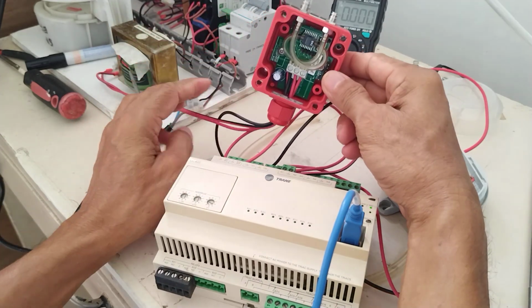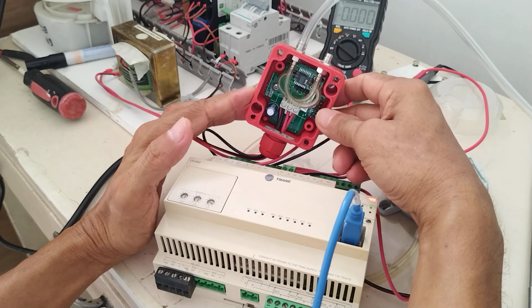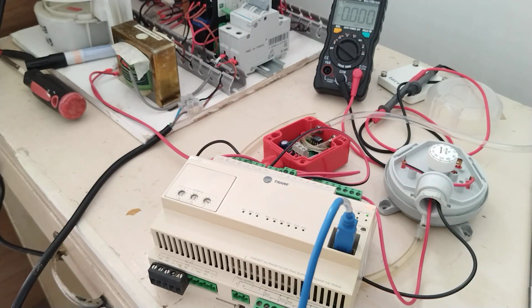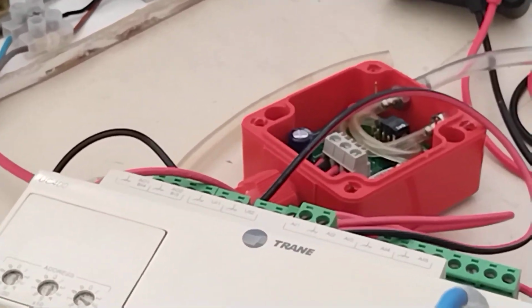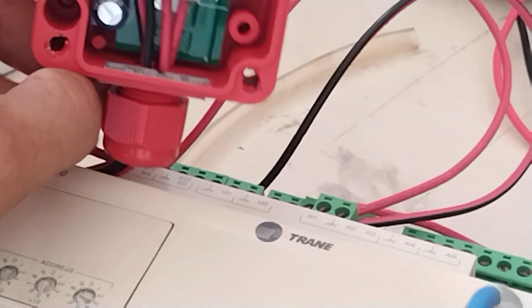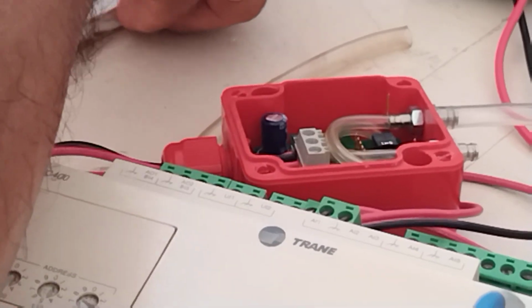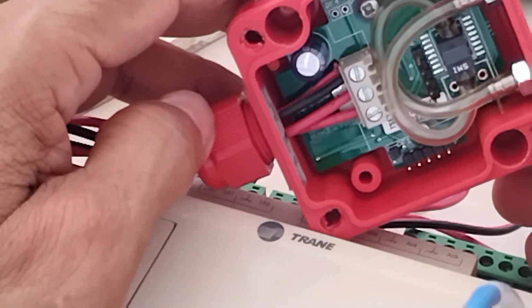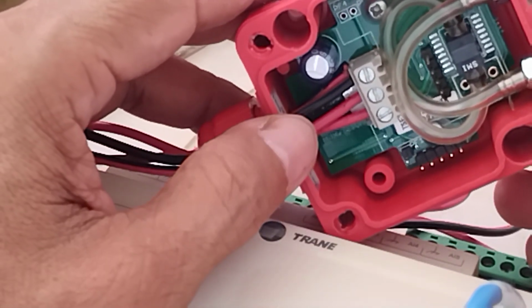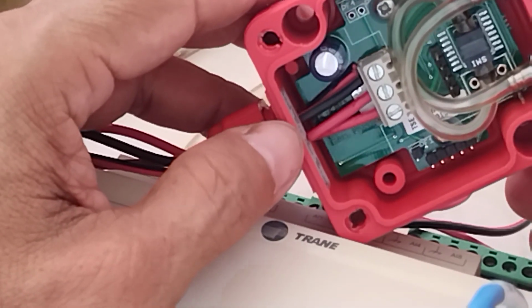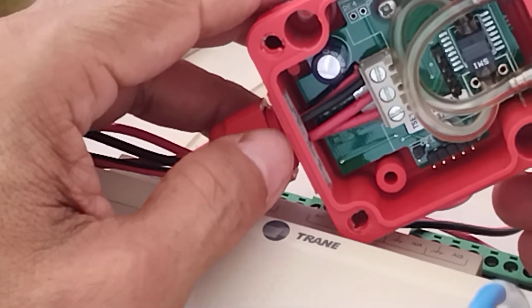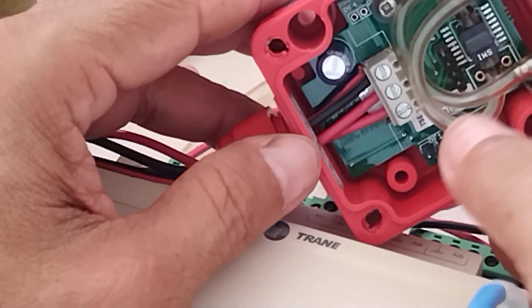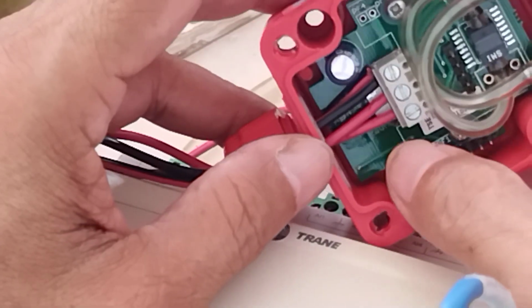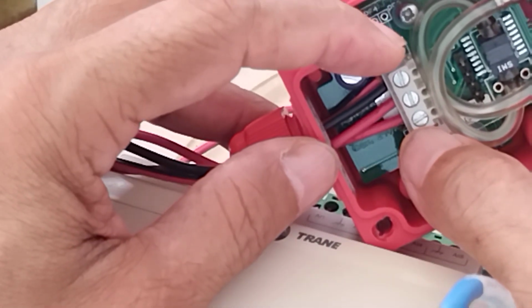So, as you can see here, I have provided here how many cables, okay? So wait a minute, let me move it a little. I have used a short wire. Now as you can see here, guys, I've used here a 4 core cable, I mean 4 wires, okay? So you can use 2 core cable, 2 numbers, okay? Because 1 and 3 will be intended for the power supply, which is 24 volts.